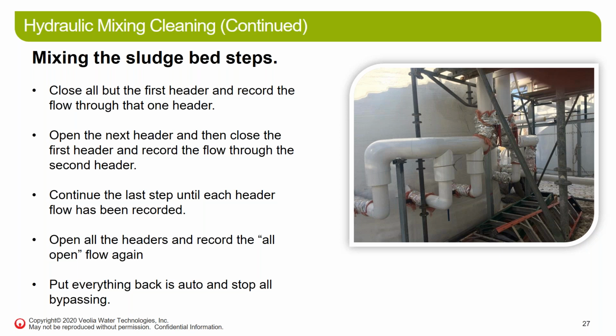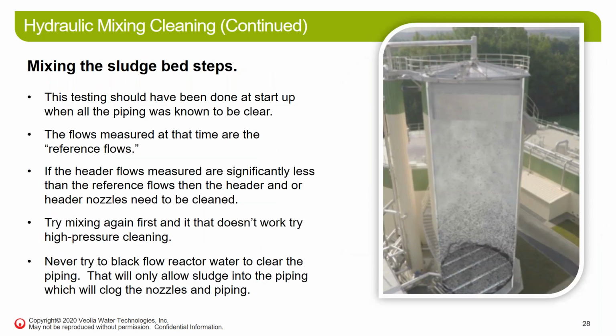After you've done this, you're going to put everything back in auto and stop bypassing anything, such as a heat exchanger or any other piece of equipment in line. You should have done this test initially at startup, when all the piping was known to be clear. So you should have a benchmark of what it was when everything was clean versus when you've just done this test. The flow measured at that time was the reference flow, your benchmark.